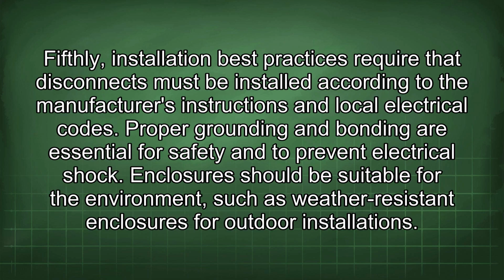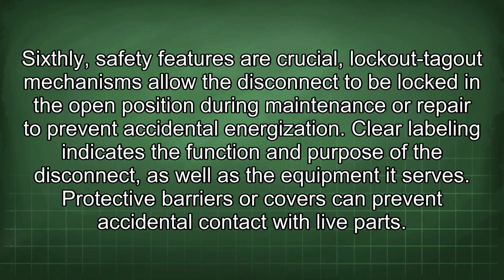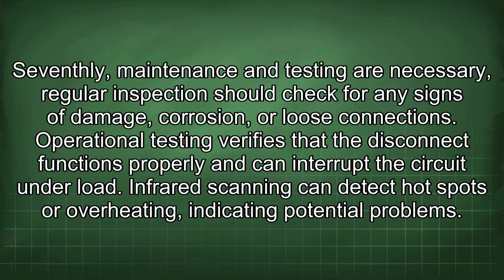Fifthly, installation best practices require that disconnects be installed according to the manufacturer's instructions and local electrical codes. Proper grounding and bonding are essential for safety and to prevent electrical shock. Enclosures should be suitable for the environment, such as weather-resistant enclosures for outdoor installations. Sixthly, safety features are crucial. Lockout-tagout mechanisms allow the disconnect to be locked in the open position during maintenance or repair to prevent accidental energization. Clear labeling indicates the function and purpose of the disconnect, as well as the equipment it serves. Protective barriers or covers can prevent accidental contact with live parts. Seventhly, maintenance and testing are necessary. Regular inspection should check for any signs of damage, corrosion, or loose connections.